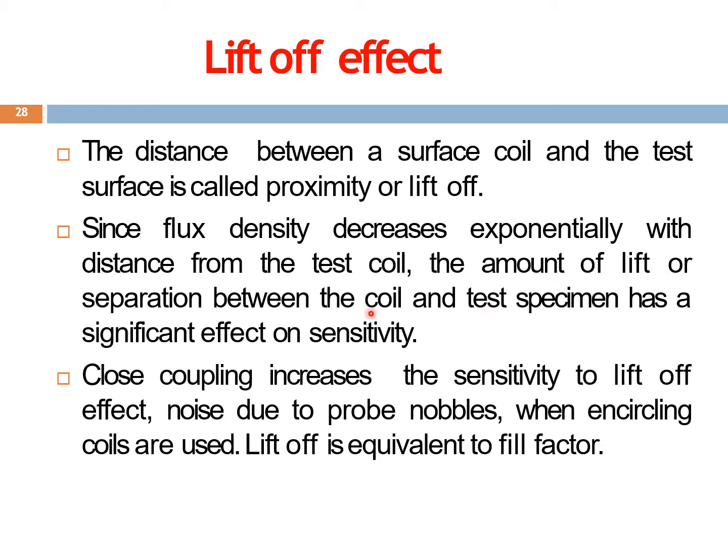The amount of lift or the separation has a significant effect on the sensitivity, resistivity. So when we decrease the distance between the surface coil and the test specimen, that is, you are decreasing the lift off distance, you'll get more accurate results. And also there is the noise due to probe wobbles when encircling coils are used. What this means is that when the probes are introduced, noises are produced.